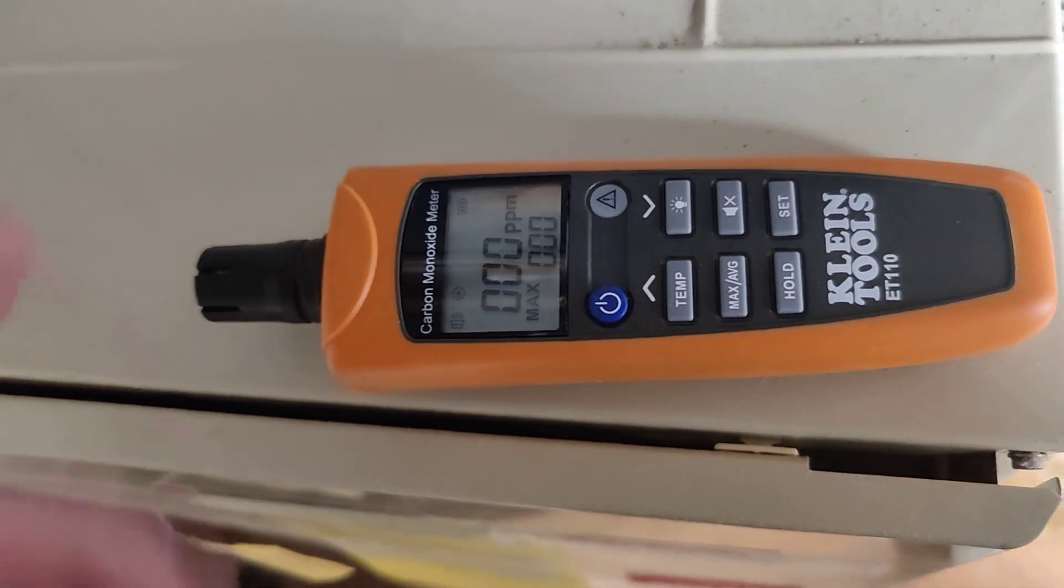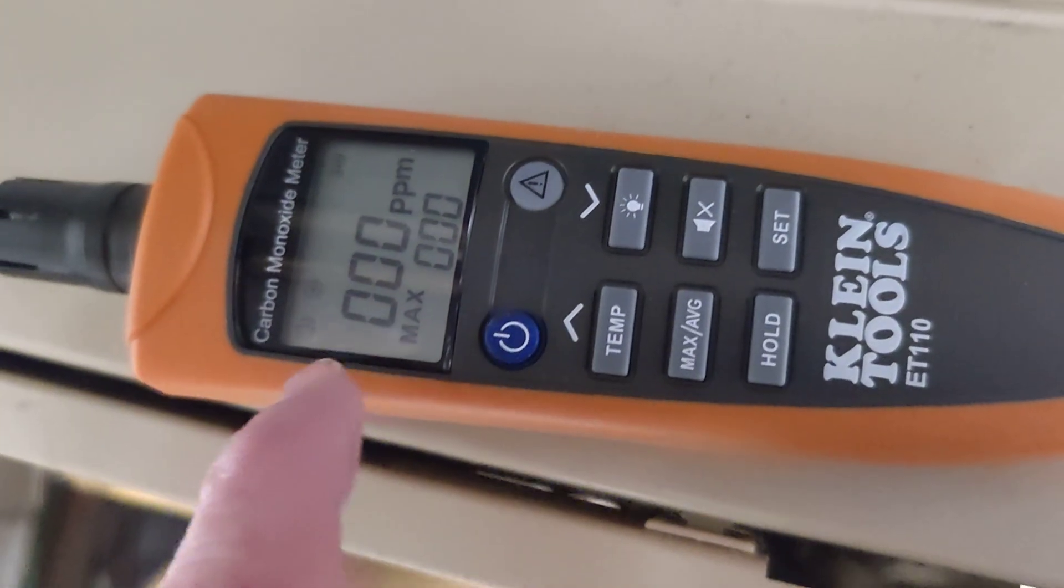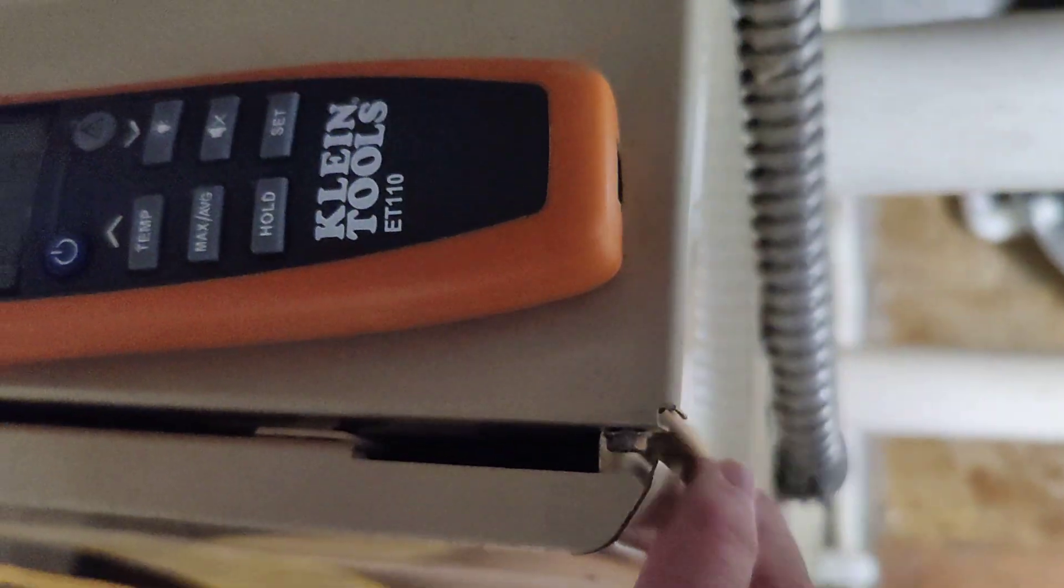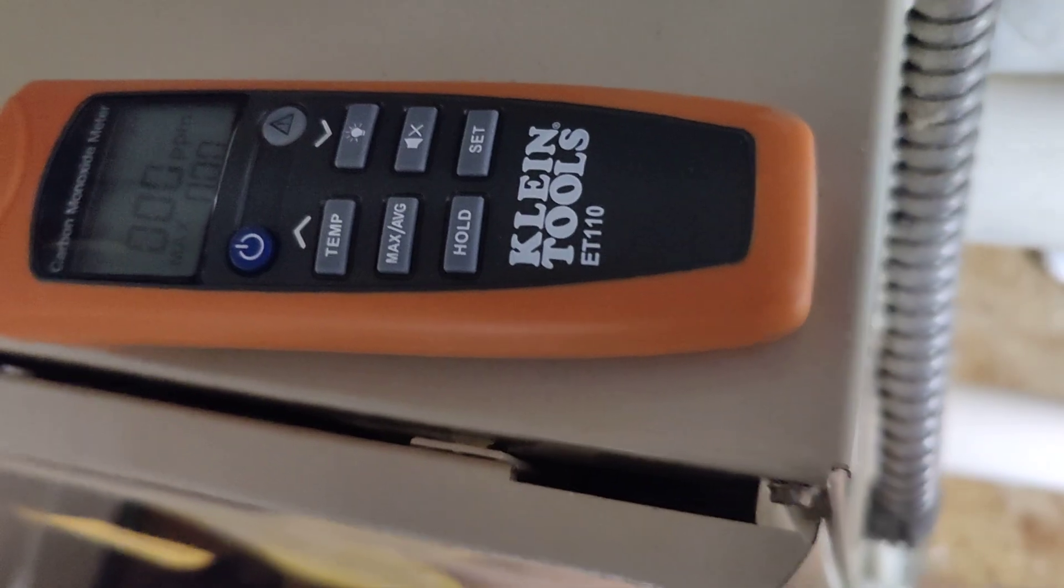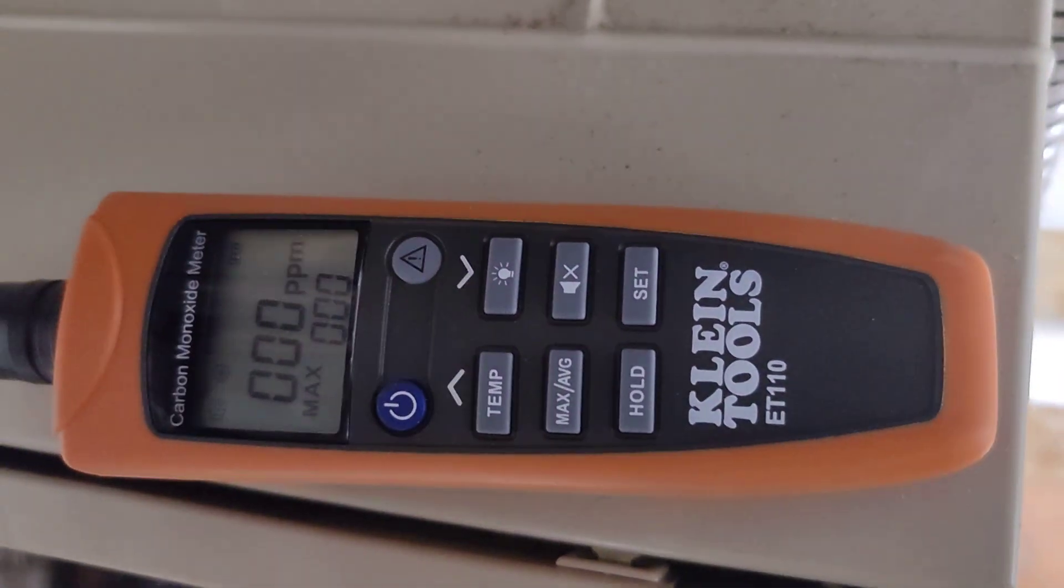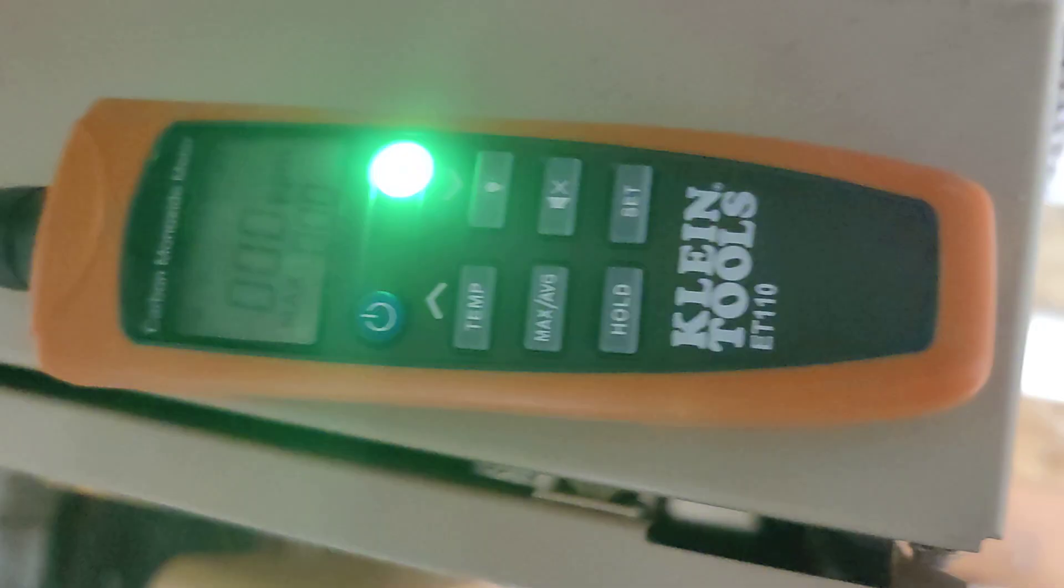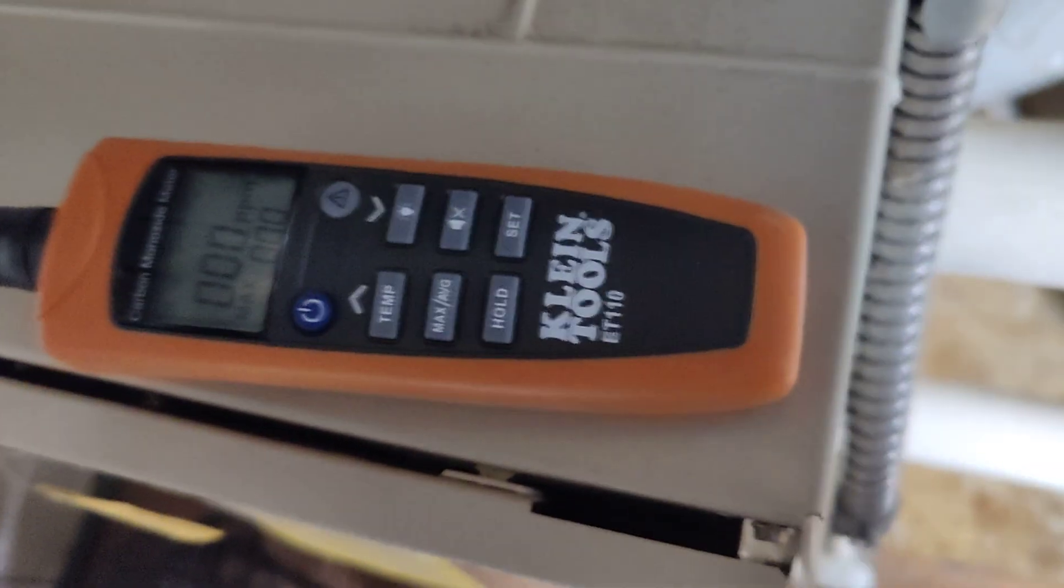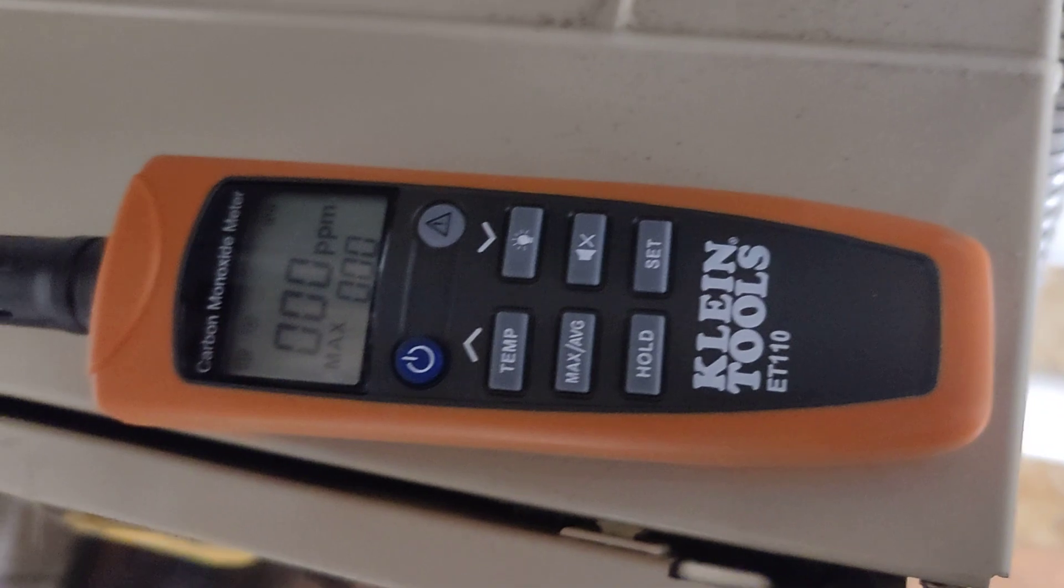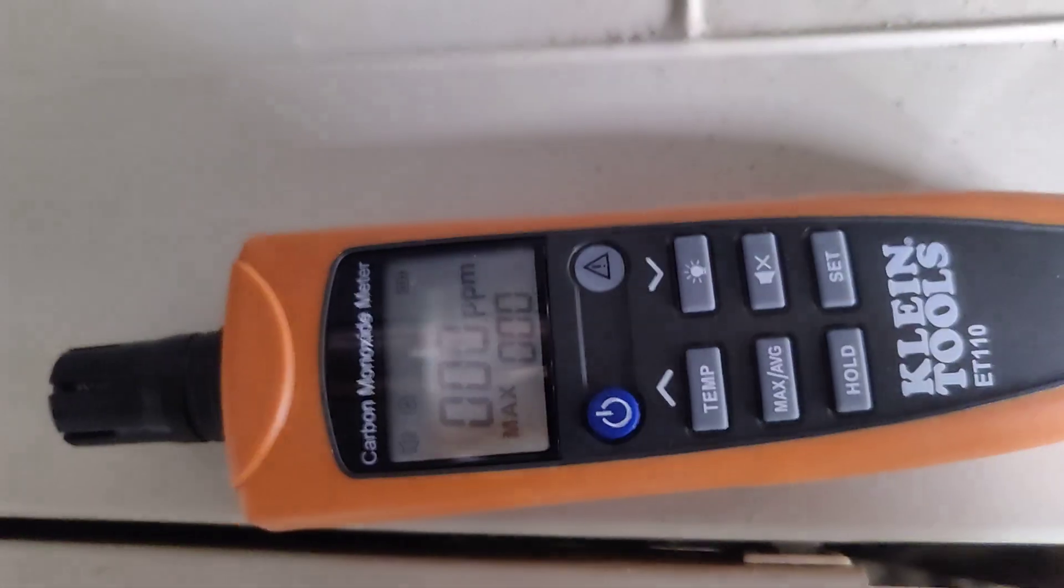If you have rollout, you'll get a reading very quick, okay? Because the rollout will be coming out of this cover, carbon monoxide will be coming out of this cover, which tells you you're going to have a cracked heat exchanger. I don't even have to go in with the scope to see your heat exchanger. You either have rollout from a cracked heat exchanger or your burners are dirty, which will cause rollout as well. Peace out y'all.